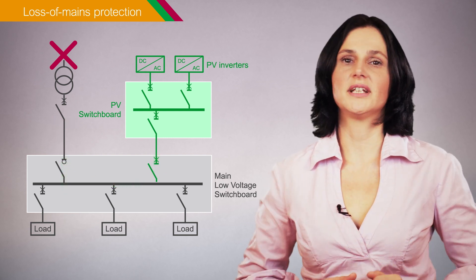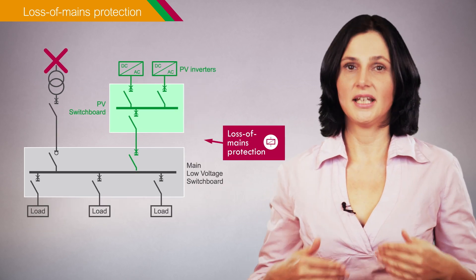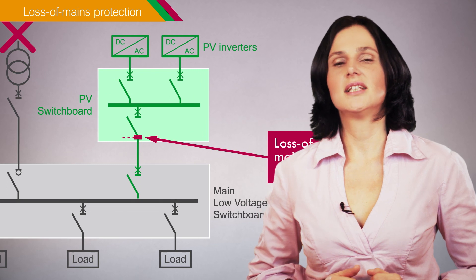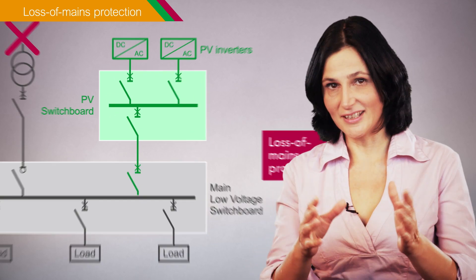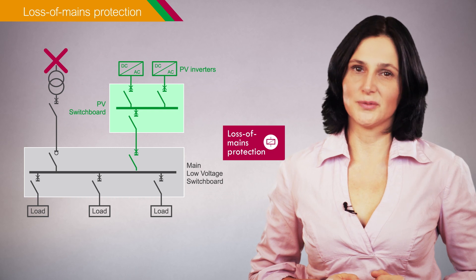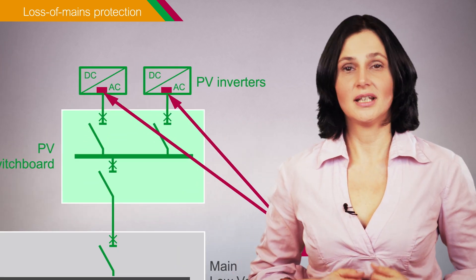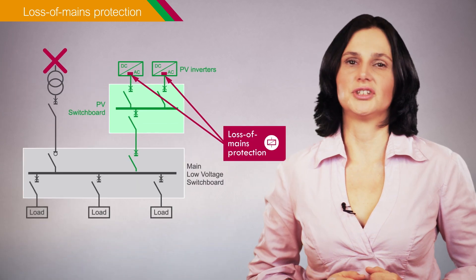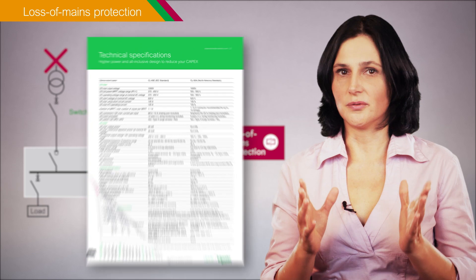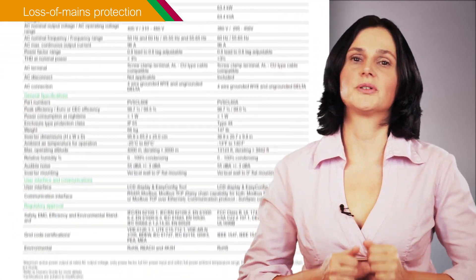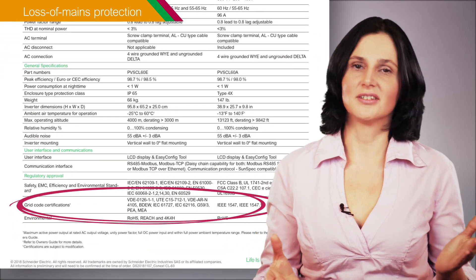Loss of mains protection can be implemented by a dedicated protection device, generally located at the photovoltaic system feeder. Another option is to use grid-type photovoltaic inverters with integrated loss of mains protection, if accepted by the energy distributor. Check the solar inverter datasheet to confirm it includes loss of mains protection and to verify appropriate standards compliance.